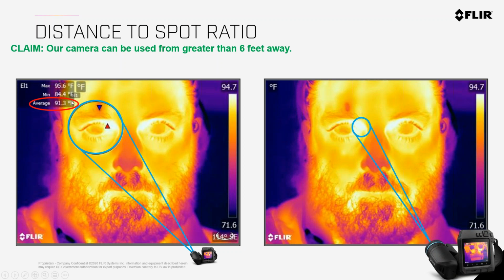If this was the extent, the camera would only read that 91.3 degrees. It takes all of the temperatures inside here and averages them to get you your 91.3, and that's obviously fairly low. Now, when we tighten up that window, when we get a better performing camera and bring it to a closer distance, you get a tighter spot and a tighter reading. Right on this spot, you're at 95.3 degrees.